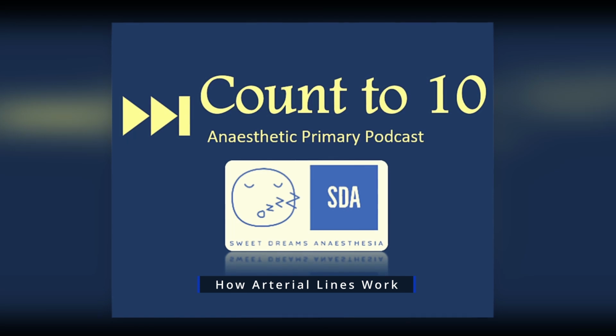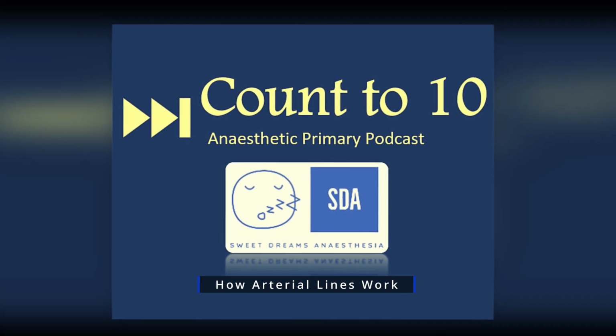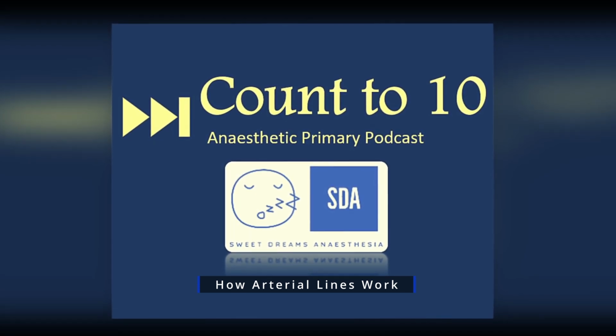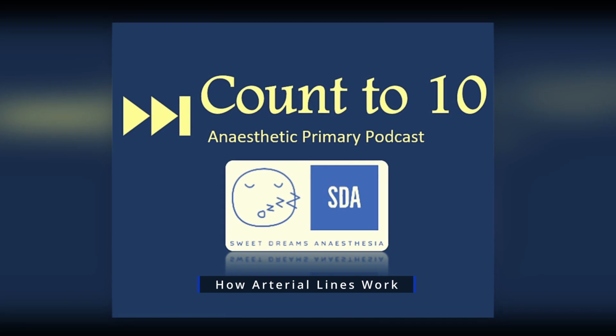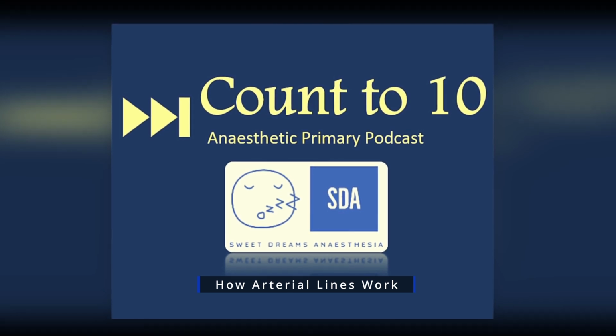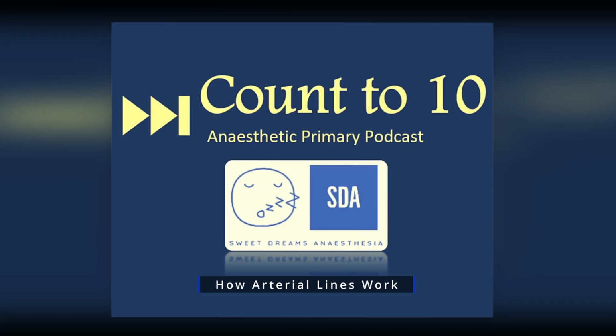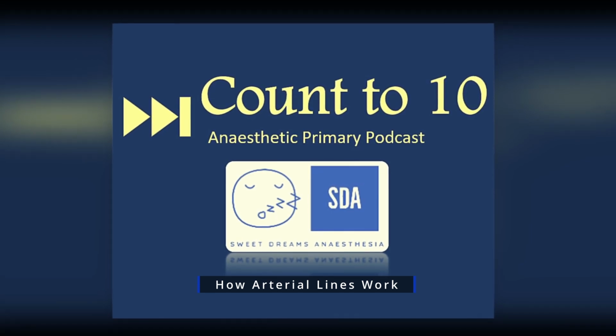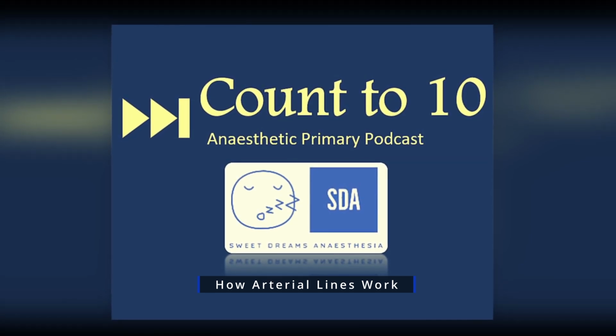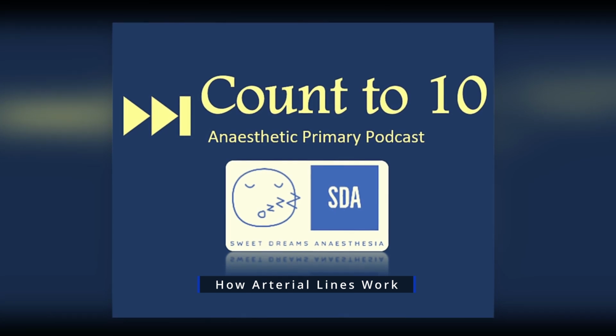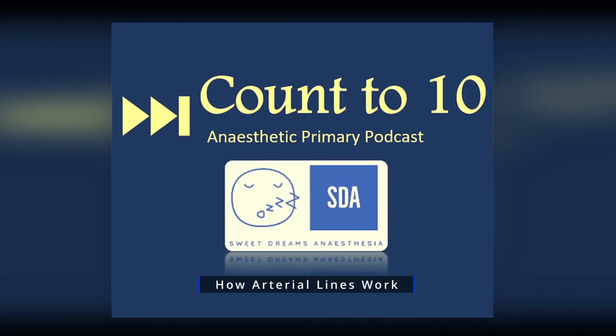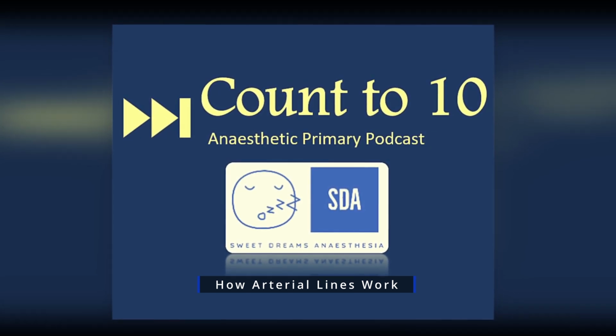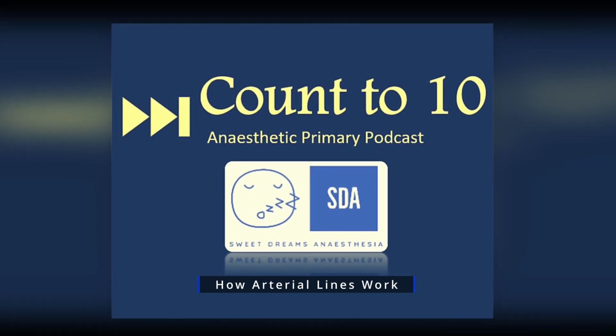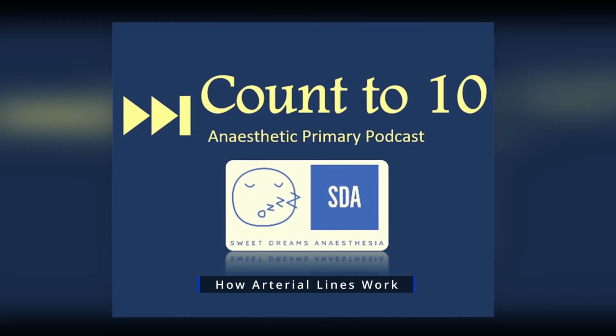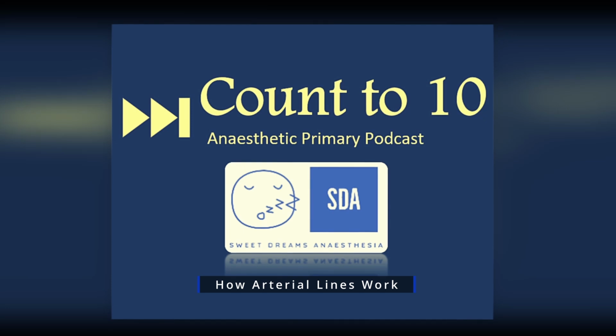So just like the transducer is a very important part of the setup of an arterial line, equally as important is the fluid-filled tubing and the tube itself. That's why arterial lines have their own specific setup, and you can't just use a normal IV line to set up an arterial line. Now the next component, being the pressure transducer, obviously has an important role in converting that arterial pressure energy into electrical energy, and we'll talk about how that happens in a little while.